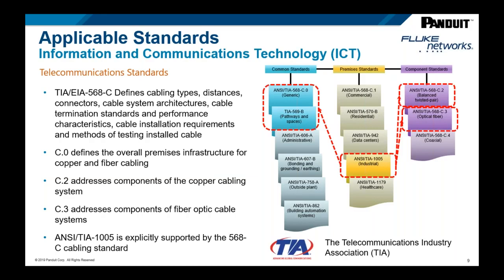You may be familiar with things that come out of the TIA standard, like the 328-foot copper limitation, which is part of the common standard 568C. The connectors used in industrial and commercial premises — whether RJ-45 or M-12, CAT-5E versus CAT-6 or CAT-6A performance, and fiber optics — are all recognized through the TIA standard. The particular standard covering industrial premises is TIA-1005A.